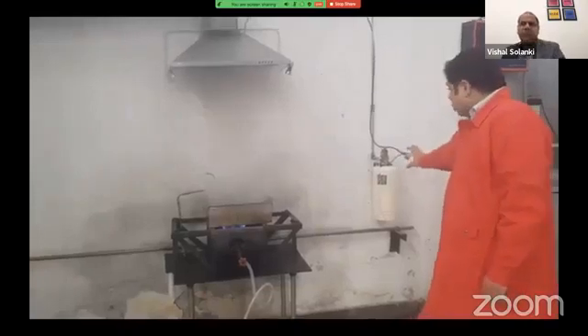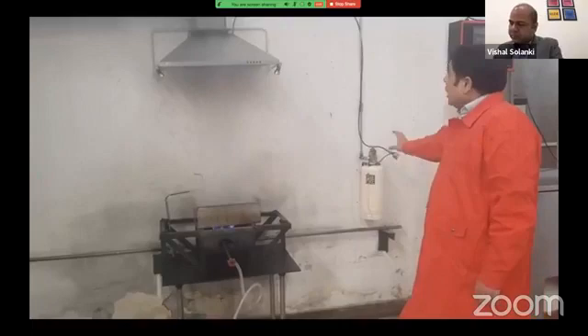We are about to have flame, and the temperature has reached about 356°C. Our cylinder with water in a stored pressure of 15 bar is ready. Our pipeline is on. Our two nozzles are aiming at the base of the fire. As soon as there is a fire, the HST is going to burst, initiate our discharge from the cylinder, and water mist is going to come directly on top of the fire and put it out.